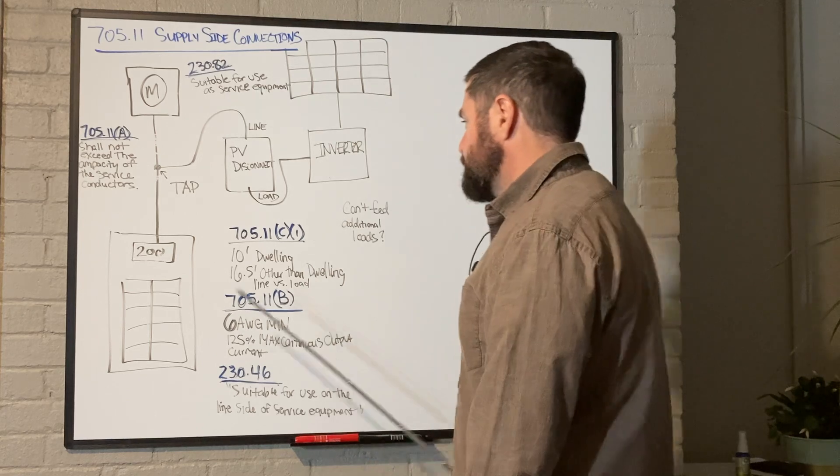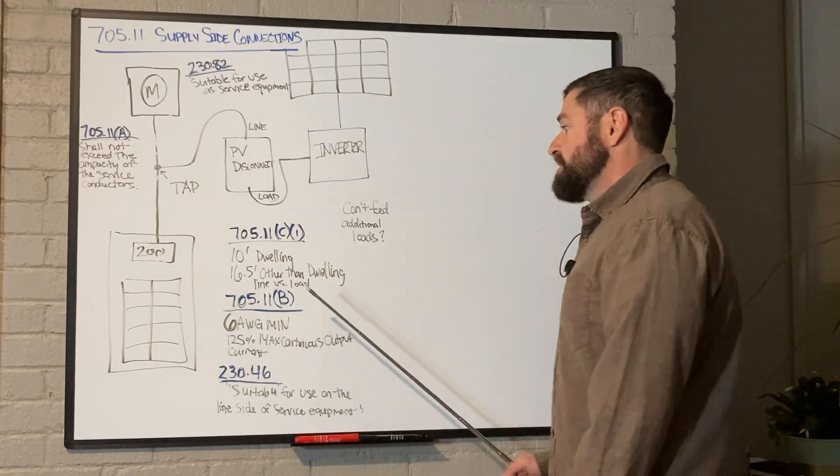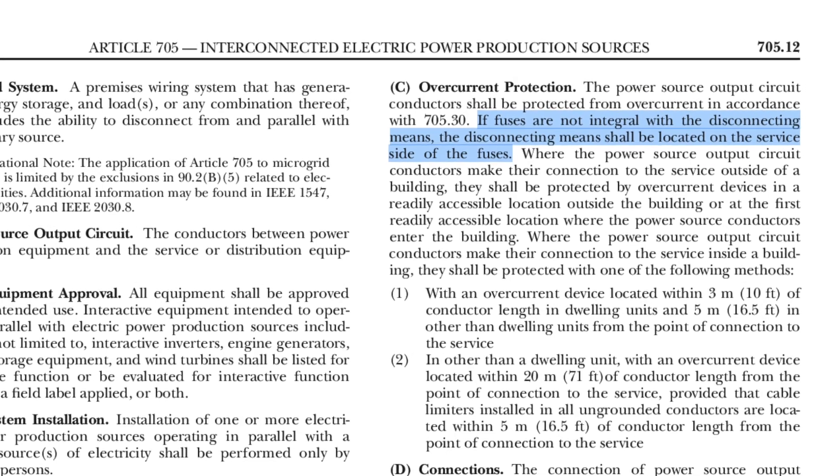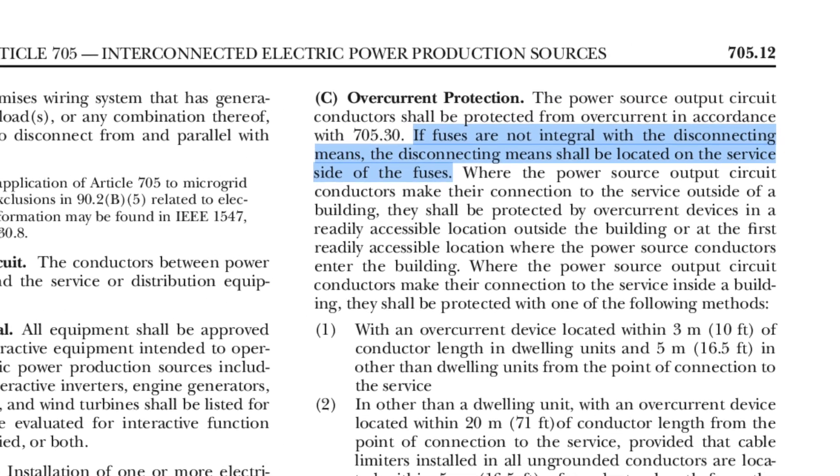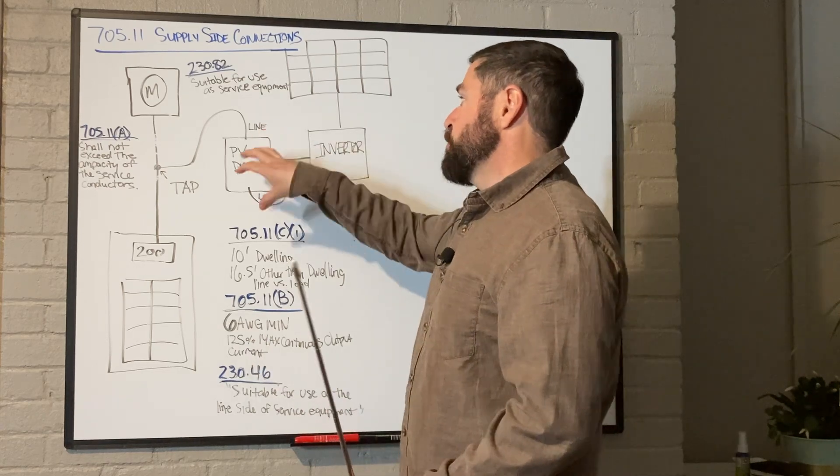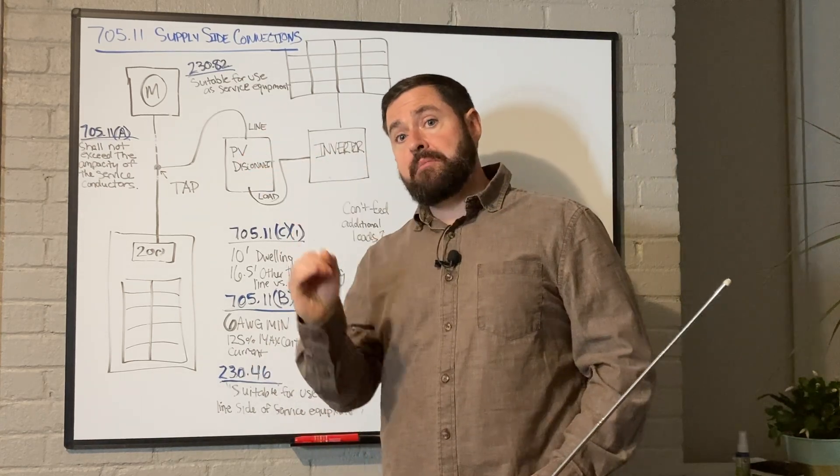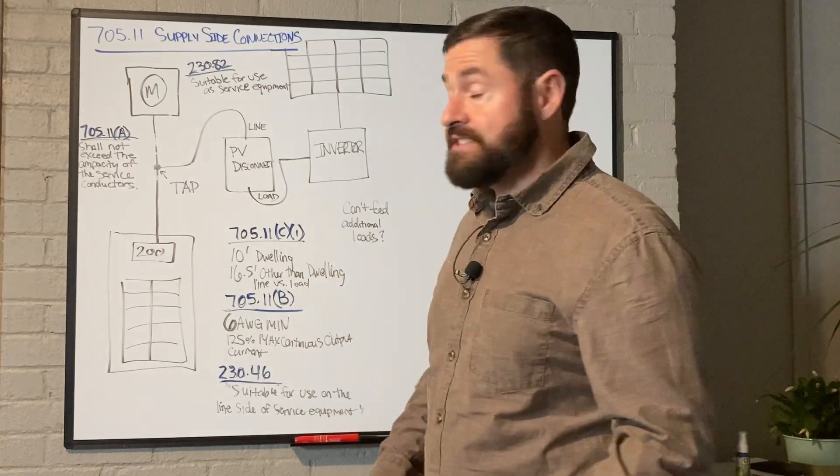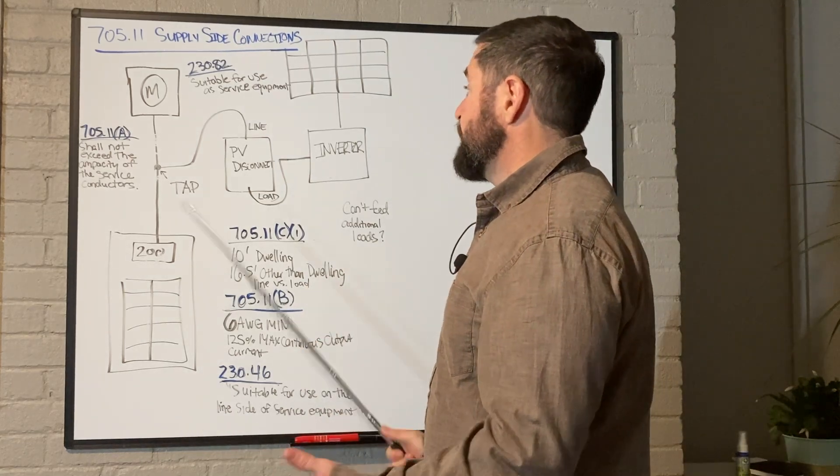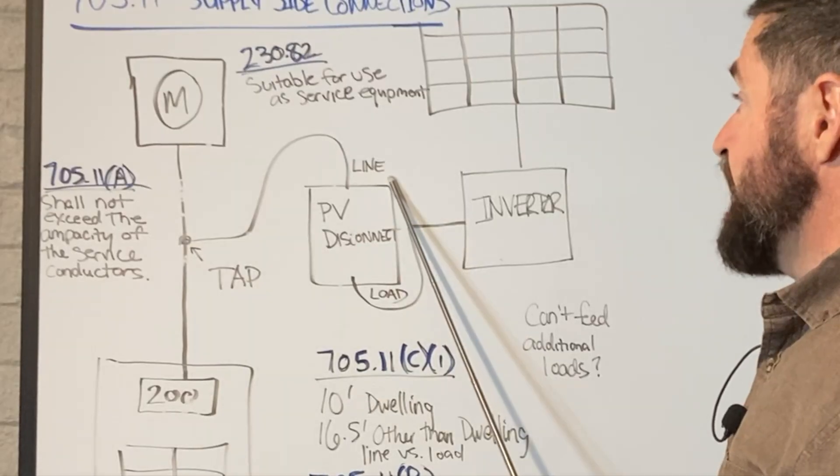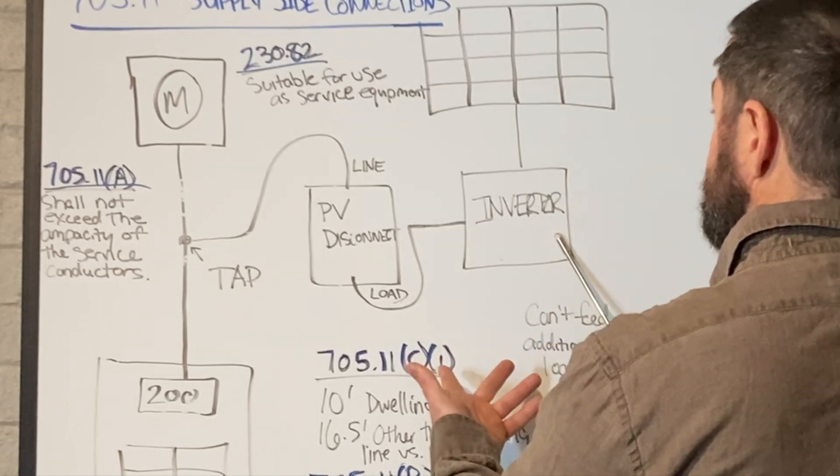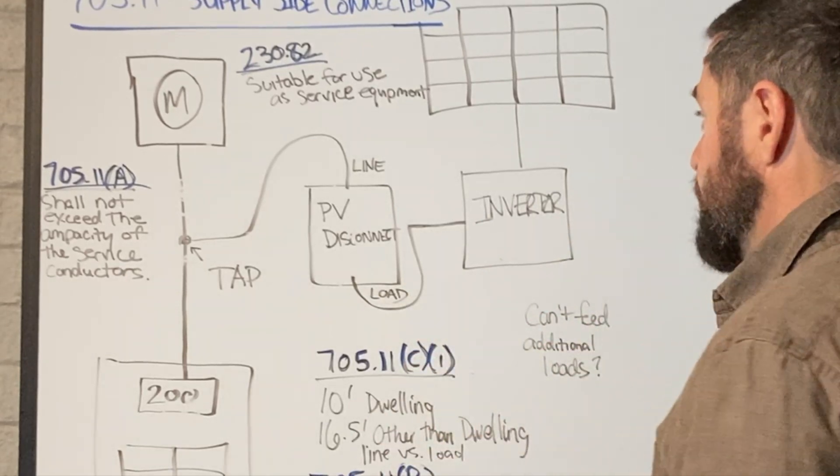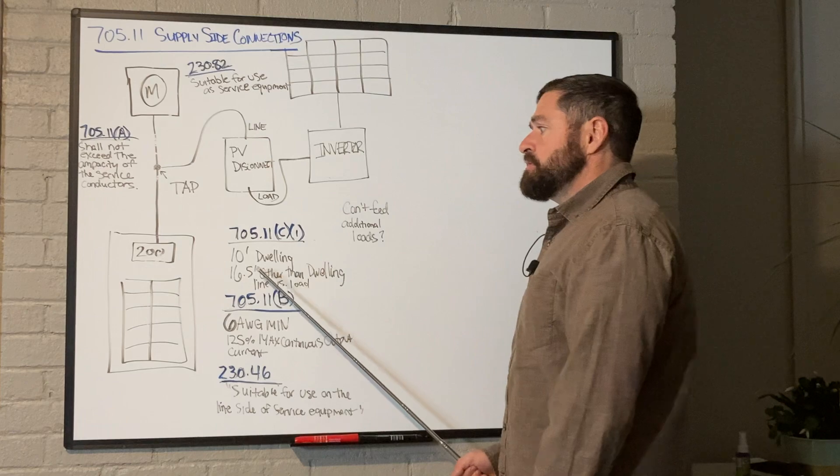Also, 705.11c1 is going over line versus load. Basically, when the PV system disconnect is in the off position, if there are fuses that are inserted in that disconnect, they have to be de-energized so that they could easily be replaced. And essentially, in order to do that, you're going to want the tap to be on the line side of the disconnect and the solar or storage system to be on the load side of the system disconnect.